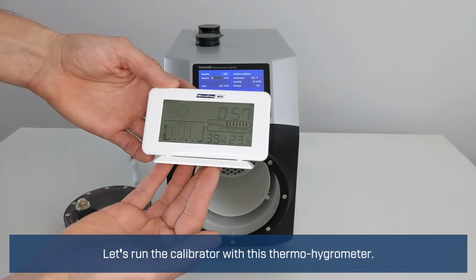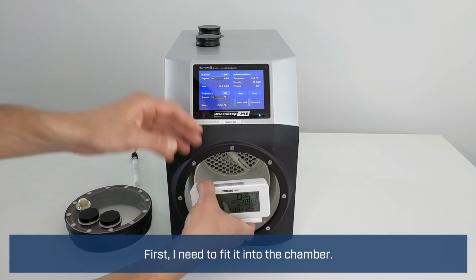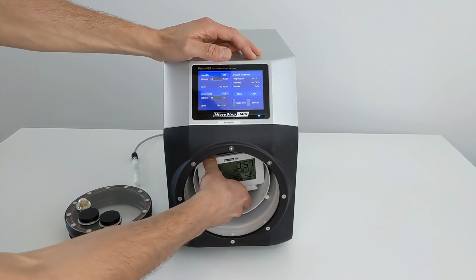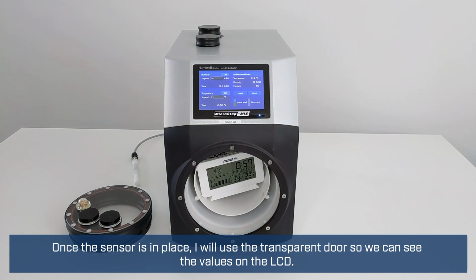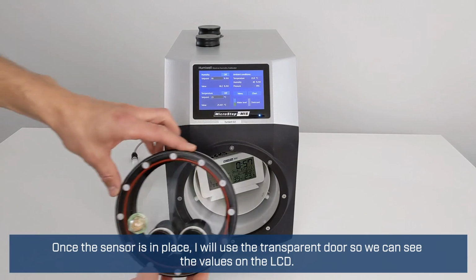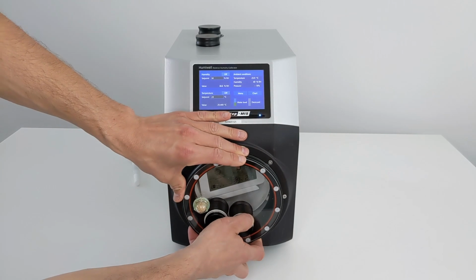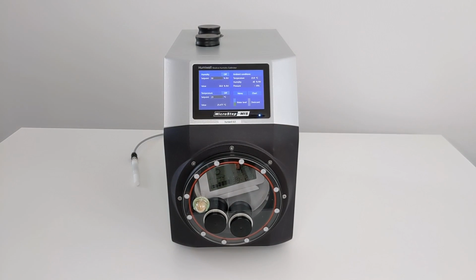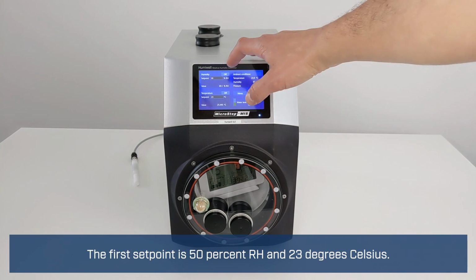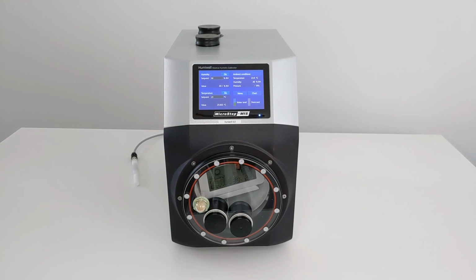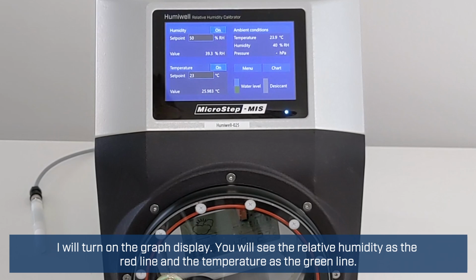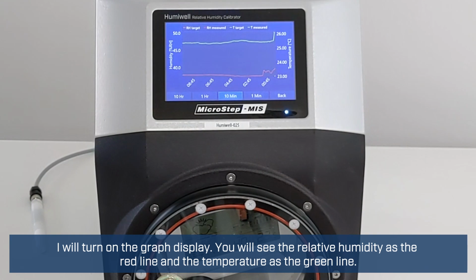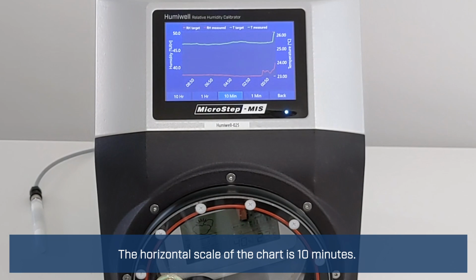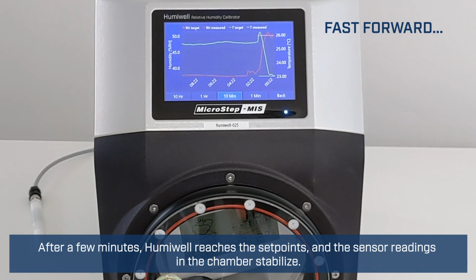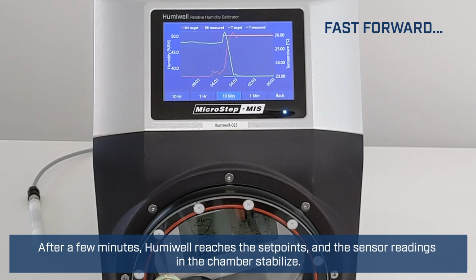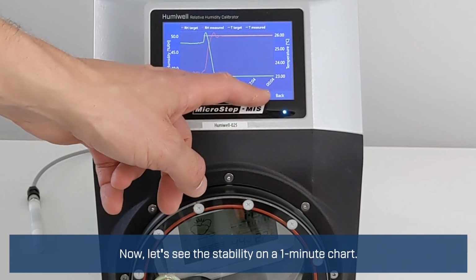Let's run the calibrator with this thermo-hygrometer. First, I need to fit it into the chamber. Once the sensor is in place, I'll use the transparent door so we can see the values on the LCD. The first set point is 50% relative humidity and 23 degrees Celsius. I'll turn on the graph display. You'll see the relative humidity as the red line and the temperature as the green line. The horizontal scale of the chart is 10 minutes. After a few minutes, Humiwell reaches the set points and the sensor readings in the chamber stabilize. Now let's see the stability on a 1-minute chart.